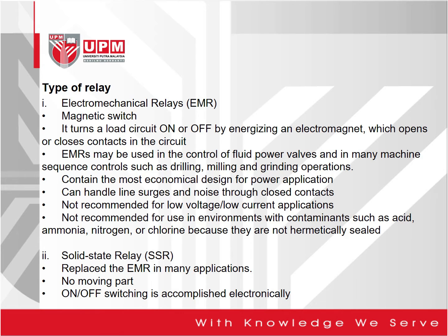It is the most economical design for power applications and can handle line surges and noise through closed contacts. It is not recommended for low voltage or low current applications, and not recommended for use in environments with contaminants such as acid, ammonia, nitrogen or chlorine because they are not hermetically sealed. And then the solid state relay, SSR, replaces the EMR in many applications. No moving parts; on-off switching is accomplished electronically.